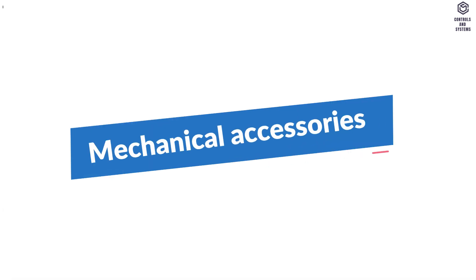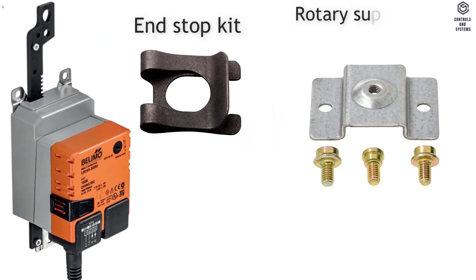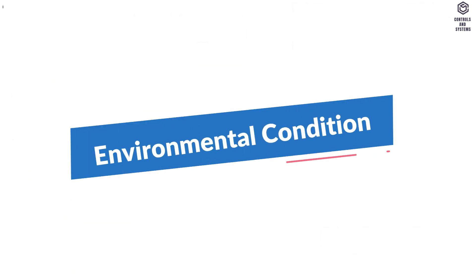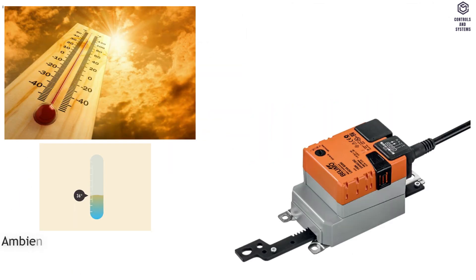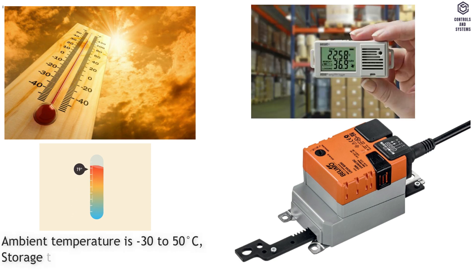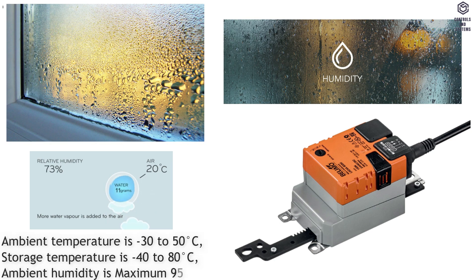Mechanical accessories include an end stop kit, rotary support for linear actuator, and coupling piece. Environmental conditions: ambient temperature is minus 30 to 50 degrees C; storage temperature is minus 40 to 80 degrees C; ambient humidity is maximum 95% RH, non-condensing.